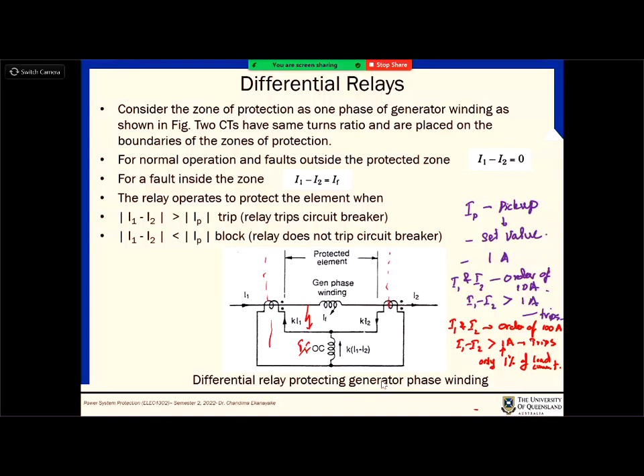As an example, using this technique you can't determine the exact location; you know that it is in between these two. But with the impedance relays, you can sometimes even tell whether it happened at the far end or this end. So you get different information from different schemes. And even current magnitudes, overcurrent relays are still used. So there are heaps of different ways. But when you are looking at transformers or generators, impedance relays don't work, and overcurrent relays are sometimes not sufficient. That's why differential relays are a must for unit protection. If you have a certain unit, differential protection is a must.